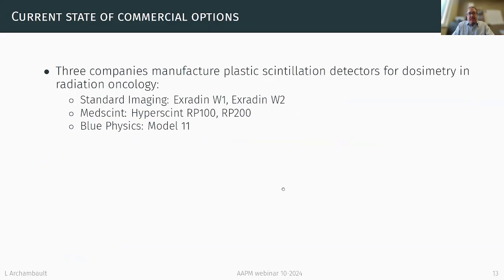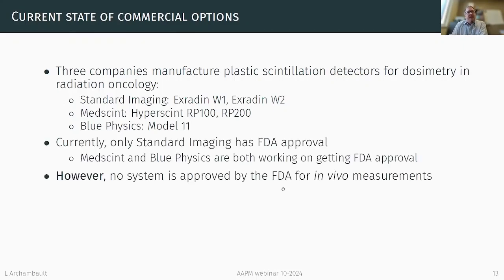So, as I've mentioned, there are 3 companies making commercial plastic scintillation detectors. Standard Imaging were the first with the Exradin W1, and then a bit later Exradin W2. MedScint with the RP100 and RP200 platforms, and Blue Physics with Model 11. So the problem is that from these 3 companies, to my knowledge, only Standard Imaging has received FDA approval, although both other companies are actively working on getting FDA approval.